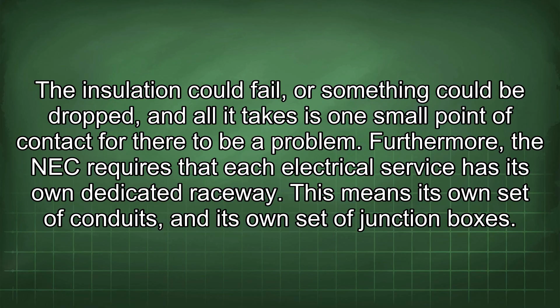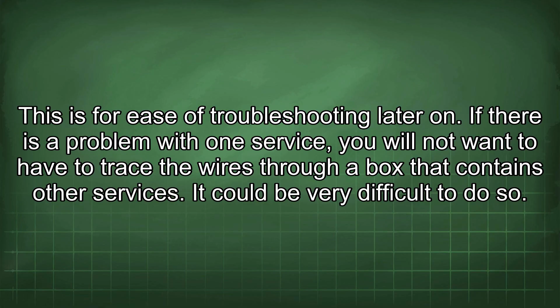Furthermore, the NEC requires that each electrical service has its own dedicated raceway. This means its own set of conduits and its own set of junction boxes. This is for ease of troubleshooting later on. If there is a problem with one service, you will not want to have to trace the wires through a box that contains other services. It could be very difficult to do so.